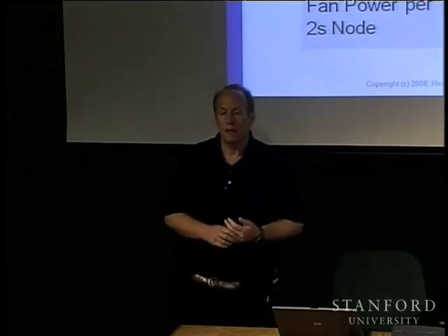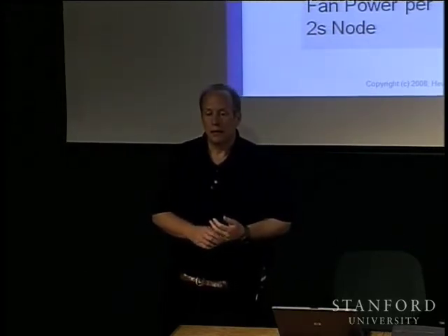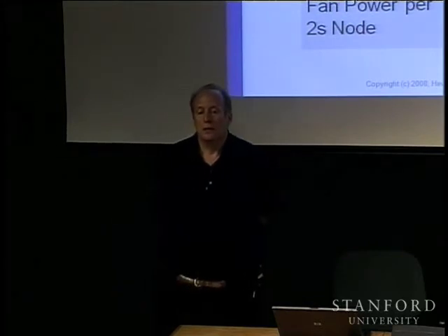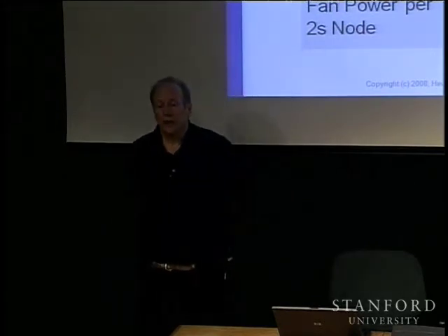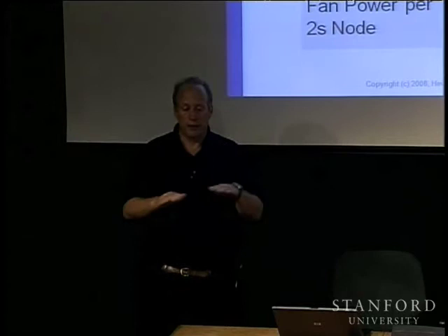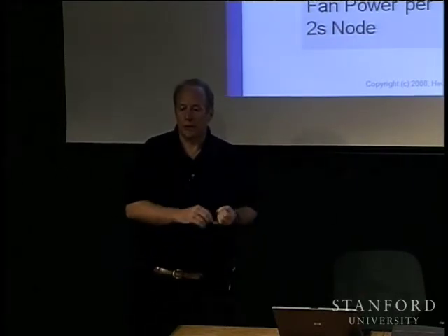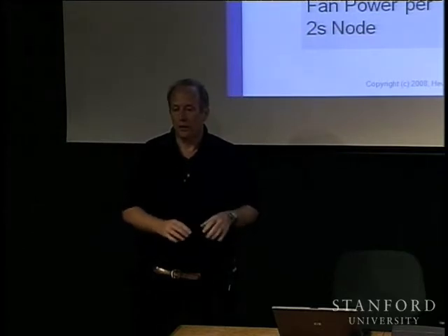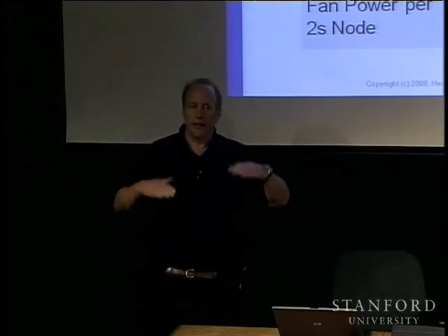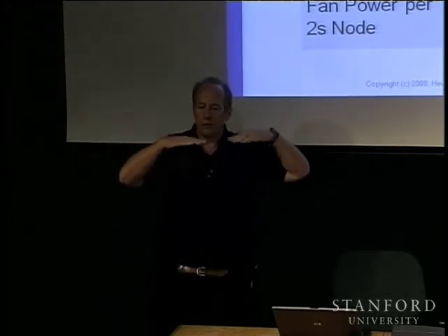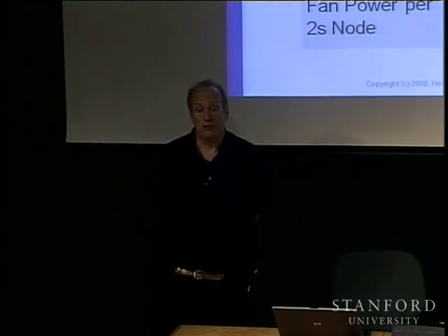Yeah, is this 92% at peak utilization, or all utilization points of the server? Good question. It's generally at peak, but the specifications are actually pretty nuanced, and they say at 10% load, 50% load, 100% load, what the percentages are. And you can make design trade-offs, and so the curves are actually getting remarkably flat. Okay.